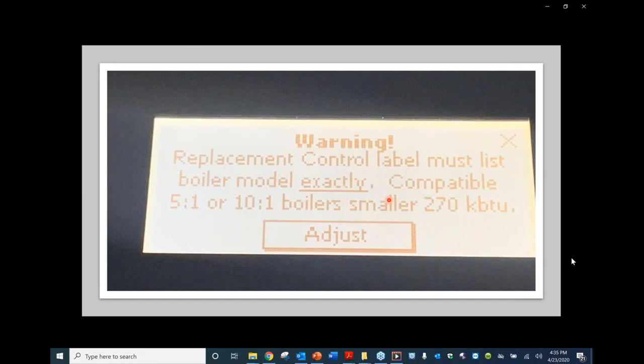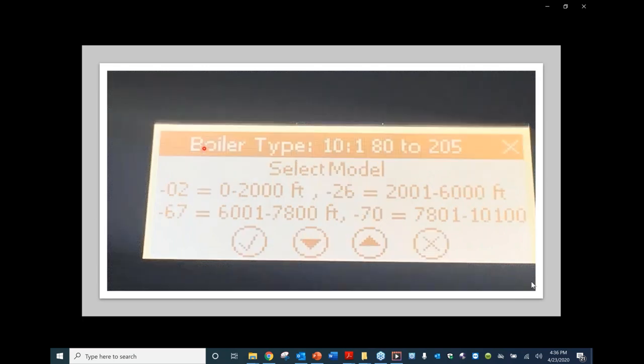When we press adjust, it's going to bring up this warning, again letting you know that the replacement control label must list the boiler model exactly, and that it's compatible with our 5-to-1 and 10-to-1 boilers smaller than 270,000 BTUs. The 10-to-1 products go from 80,000 to 205,000. We're going to press adjust, and it brings us to this screen. It tells us the boiler type is a 10-to-1 boiler, 10-to-1 turn down ratio, and 80 to 205,000 BTUs.